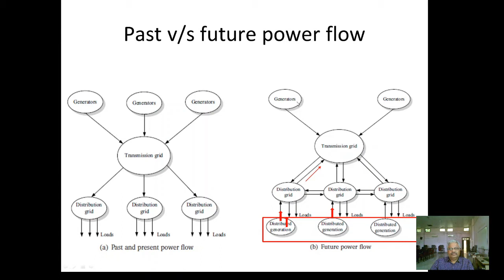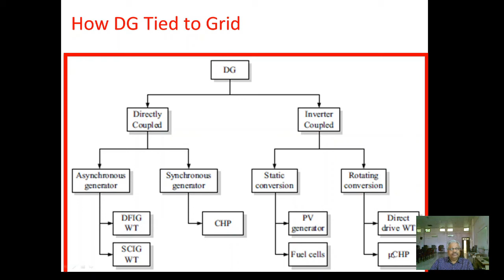There are two ways, either directly coupled or inverter coupled. In directly coupled, an asynchronous generator or synchronous generator is there. And in inverter coupled, static conversion or rotating conversion is there. Now, an asynchronous generator tie is for DFIG wind turbine or SCIG wind turbine. Synchronous generator tie is for combined heat and power plant. Static conversion, what we generally call an inverter, is used for PV generator or fuel cells. And rotating conversion, we connect direct drive wind turbine and micro combined heat and power.